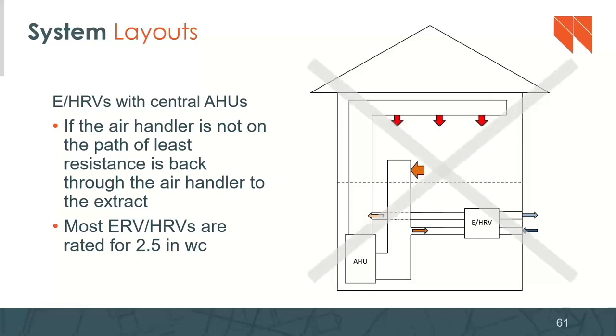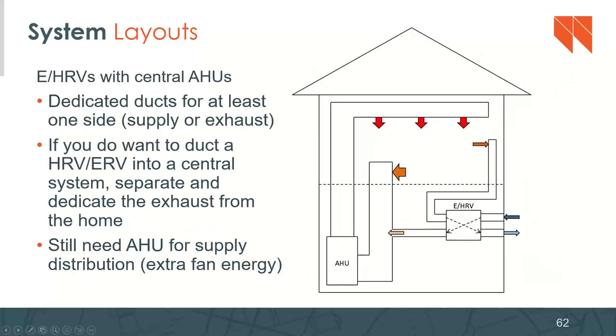We don't think this is a very good idea either, because usually this ERV, HRV is not going to be able to overcome the 2.5 inches. They're only rated for 2.5 inches of water column. The return side of this air handler is going to have a static pressure that exceeds that. So how could you potentially integrate your ventilator into your heating and cooling ductwork?